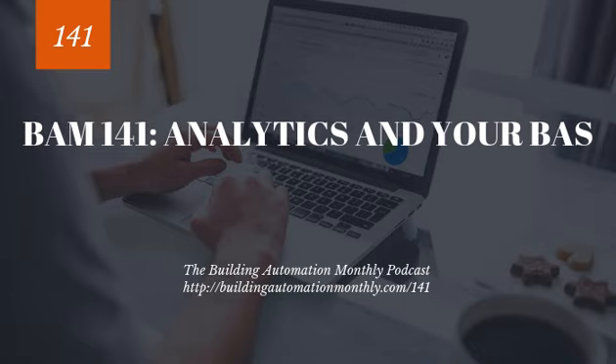Whenever you get a demonstration from analytics providers and they show you their analytics solution, they're going to typically show you one of 4 analytics case studies. They're going to show you simultaneous heating and cooling because, oh my gosh, if you're heating and cooling at the same time, you're going to waste BTUs. Or they're going to show you an outdoor air damper that's open and leaking through. Oh my goodness, we're getting cold or hot air in the building. Or they're going to show you a door's been left open. Oh my gosh, who would have known? Door open all night. Or they're going to show you, oh look, these systems are running when they shouldn't be running. Okay, yeah, I get it.